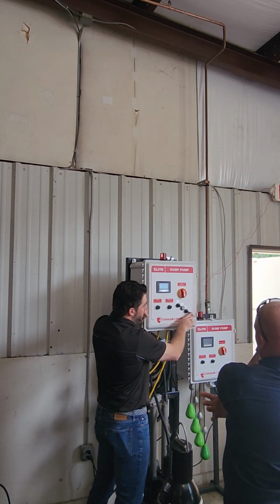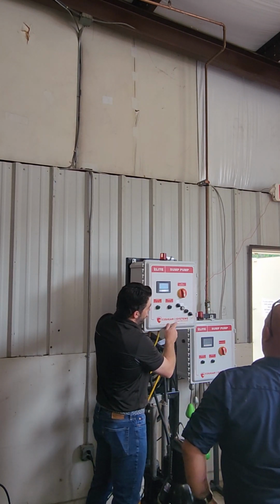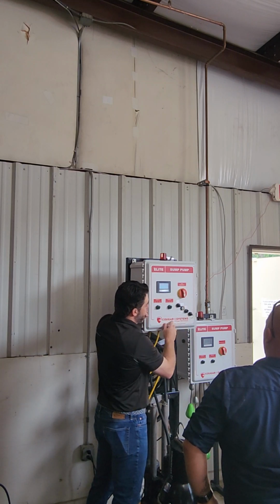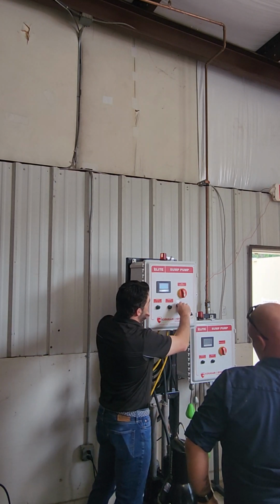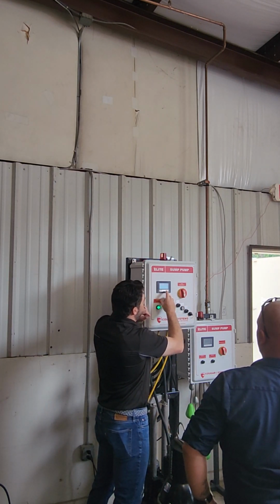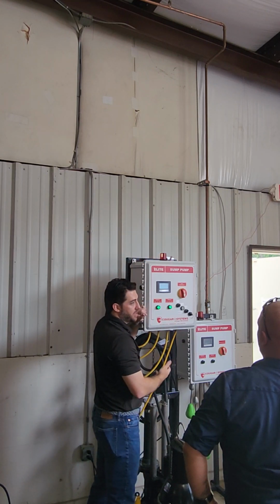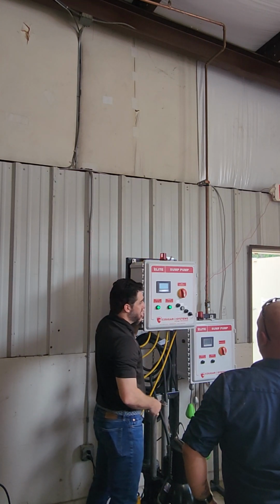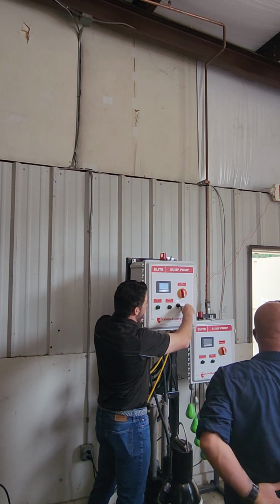Let's say this bottom float switch doesn't work, and we hit the next one, it doesn't turn the pump on, this one doesn't turn the lag on. But if we get to the high level alarm, it's going to turn on both pumps and give you the alarm. So you got that backup in case you have an issue. I think that's a better system.